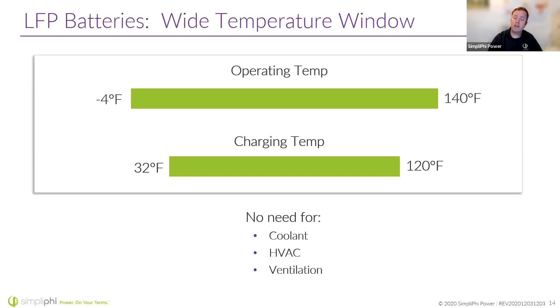Check out our pre-recorded trainings on the YouTube channel. Keep an eye out for upcoming trainings on these. The ways we can mitigate cold temperatures are heating pads and insulated battery cabinets. We start to talk about understanding the temperature gradients between inside and outside the battery cabinet. There's no need for a coolant, HVAC, and ventilation. So there's no need for that vent fan to get rid of that hydrogen. Again, these are all other modes of failure that we don't need to worry about in our battery system.